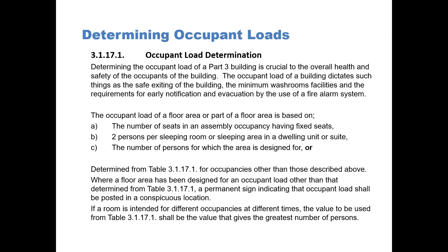The occupant load of a floor area or part of a floor area is based on: A, the number of seats in an assembly occupancy having fixed seats; B, two persons per sleeping room or sleeping area in a dwelling unit or a suite; C, the number of persons for which the area is designed for; or they can be determined from Table 3.1.17.1 for occupancies other than those described above.